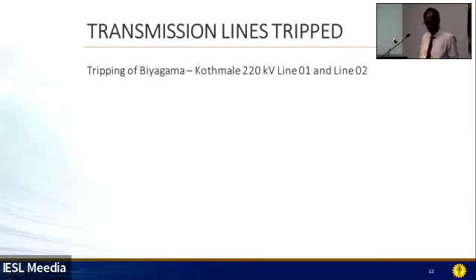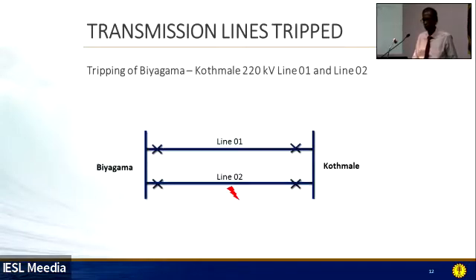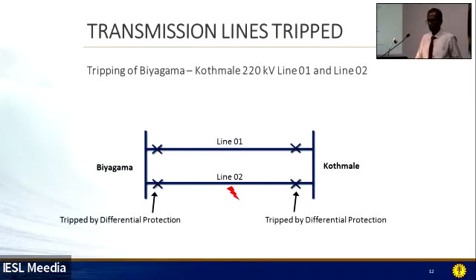First, I will explain the operation of relays in the Biyagama Kotmale 220 kV line 1 and 2. What you have first observed is that in line 2 there was an earth fault current from B phase to ground, as per records available from protection relays as well as digital disturbance recorders. Because of this B phase to earth fault in line 2, differential relays installed at both ends of the line detected the fault, tripped that particular phase of that line and isolated the faulty condition from the network.